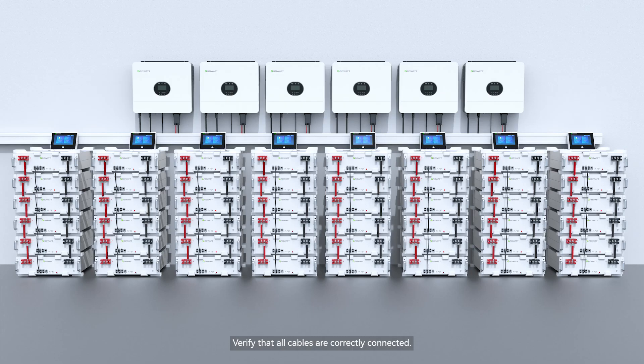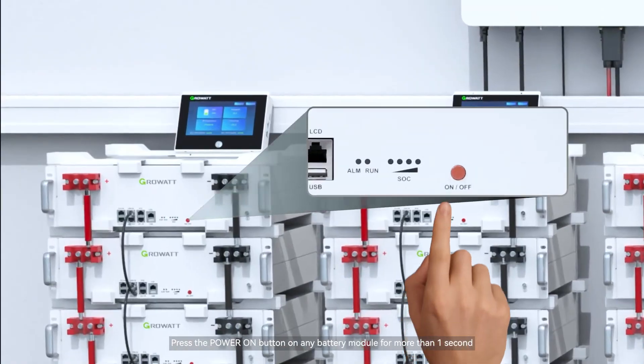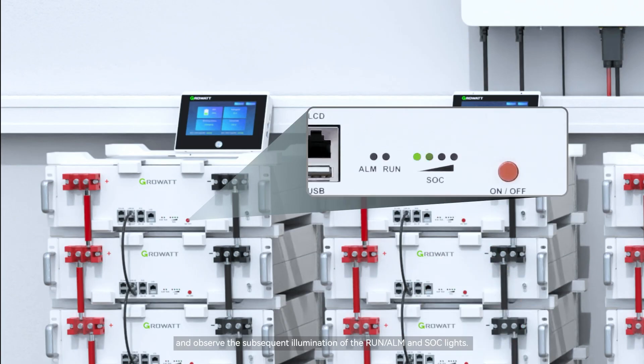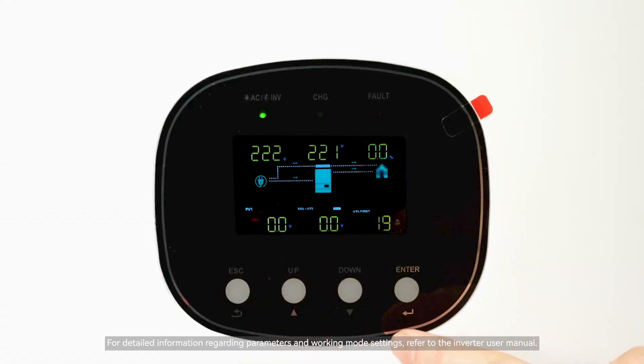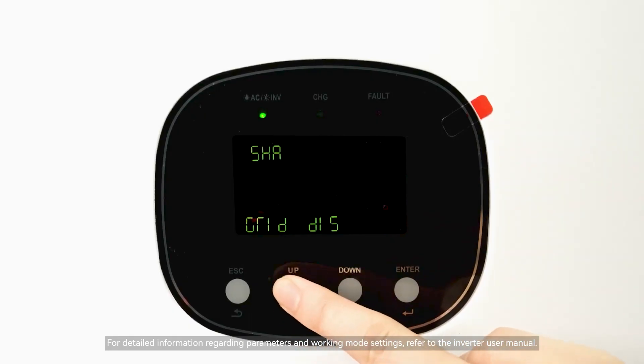Verify that all cables are correctly connected. Press the power on button on any battery module for more than one second and observe the subsequent illumination of the RUN, ALM, and SOC lights. Wait about 5 seconds, then press the inverter on/off button to start the energy storage system. For detailed information regarding parameters and working mode settings, refer to the inverter user manual.